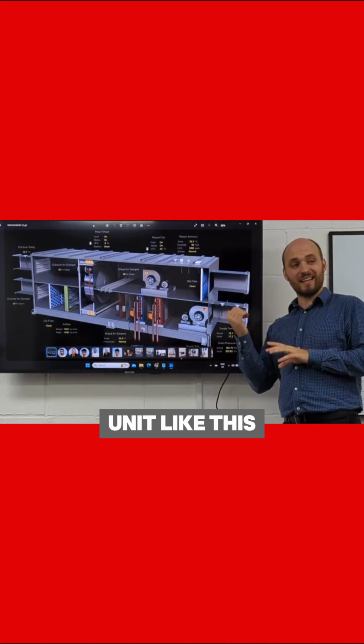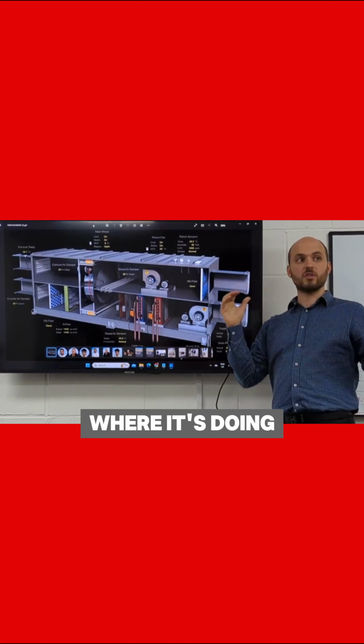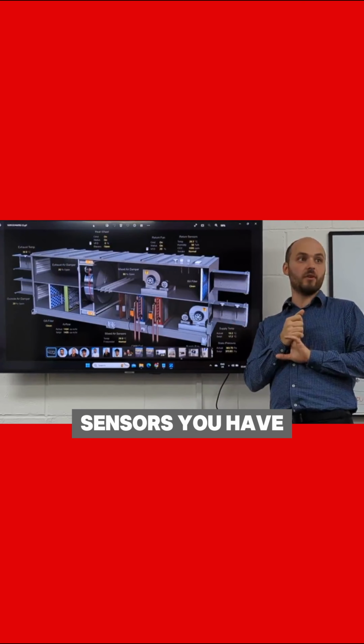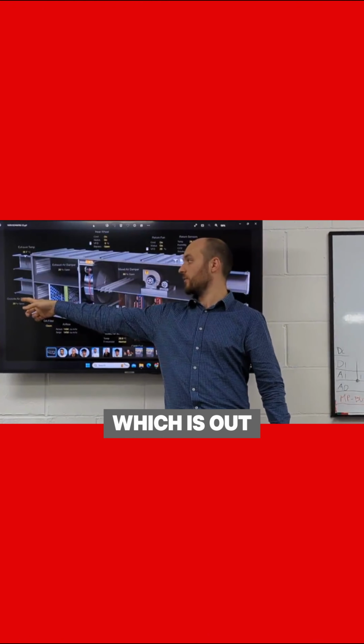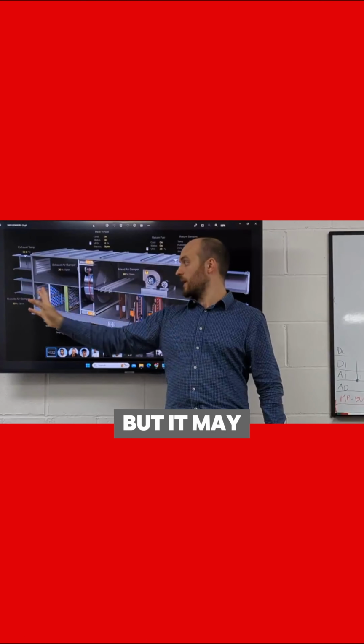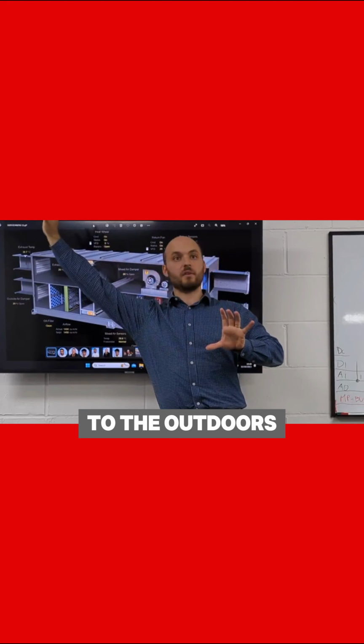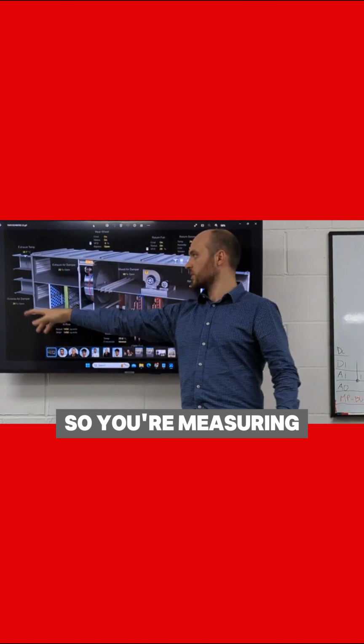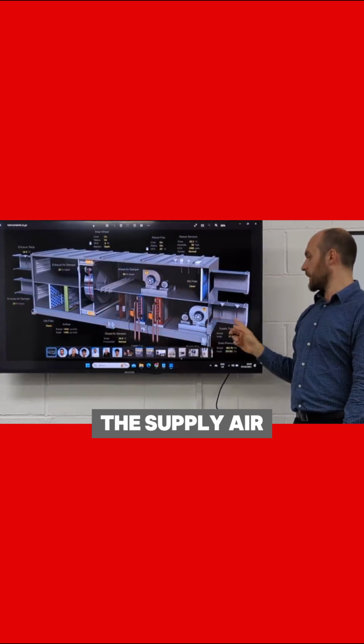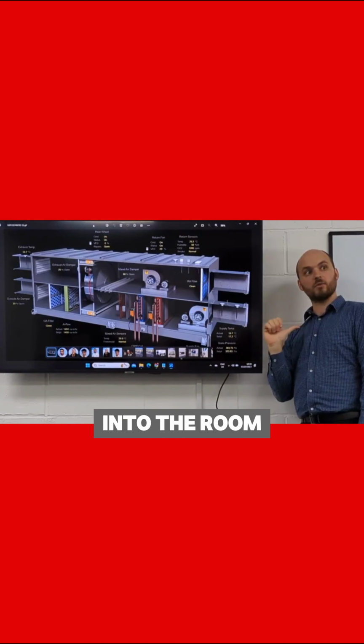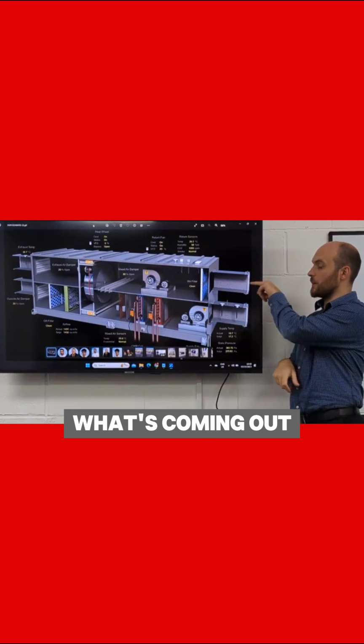Typically, for a unit like this, where it's doing supply and exhaust, you'd have 3 sensors. You have one here, which is measuring the outside air temperature. It might not actually be outside, but it may be on this duct, which is connected to the outdoors, basically. So you're measuring the outdoor temperature, the supply air temperature, what you're supplying into the room, and the exhaust temperature, what's coming out of here.